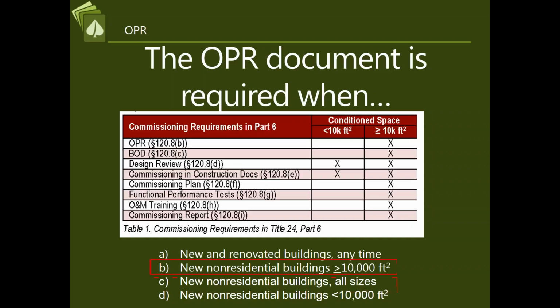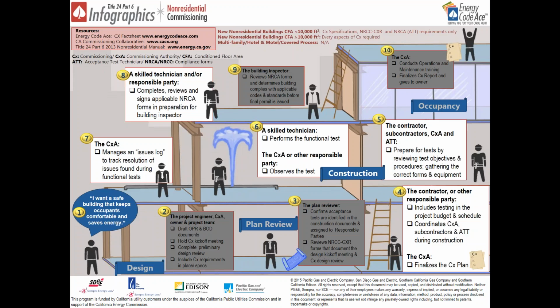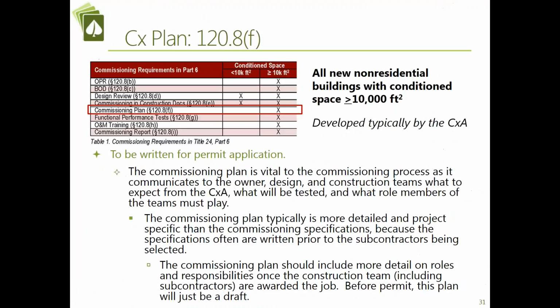So now let's move on to what happens during construction. Now that we've set the stage and we've let everyone know this is what we want, the building owner's like, hey, I have certain requirements I want to have in place with my building. I'm spending a lot of money to do it. Let's make sure they're actually being integrated during construction. So the commissioning plan basically is setting out what was established with the specification and says, now this is exactly how it's going to happen. This is when so-and-so is going to do this. This is what needs to be in place before this is tested, and then after that is tested, this needs to be the next thing that's done. It has to be very detailed.